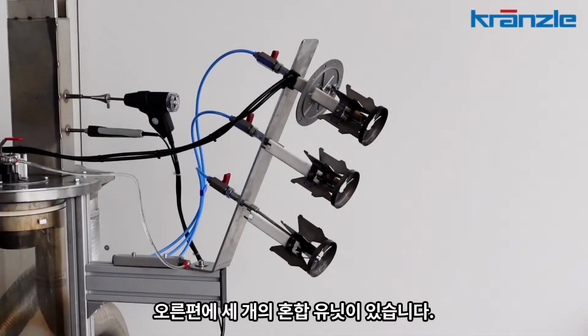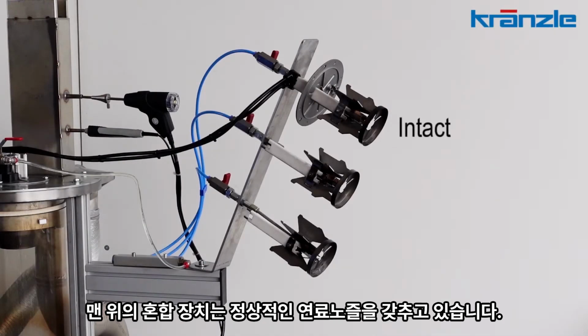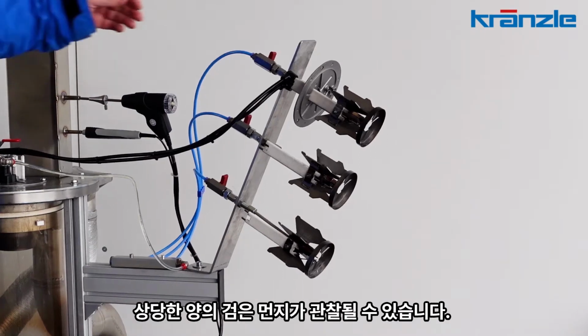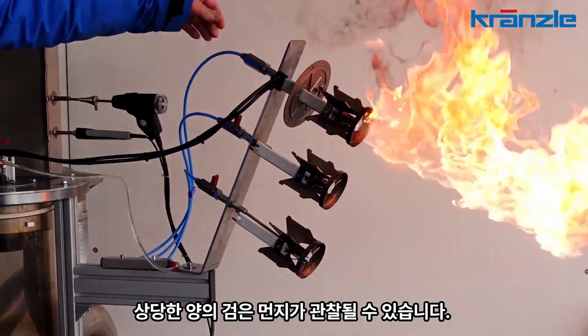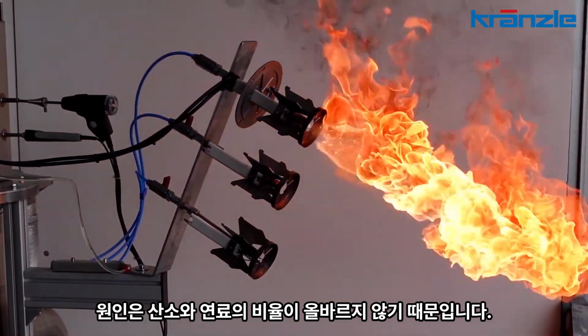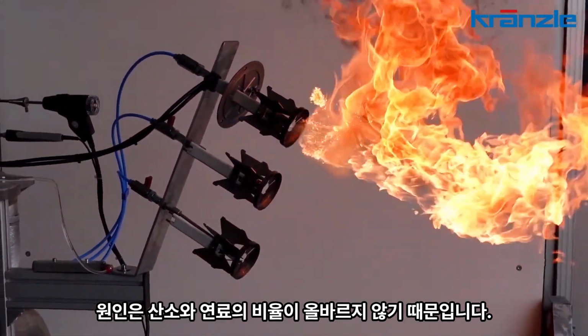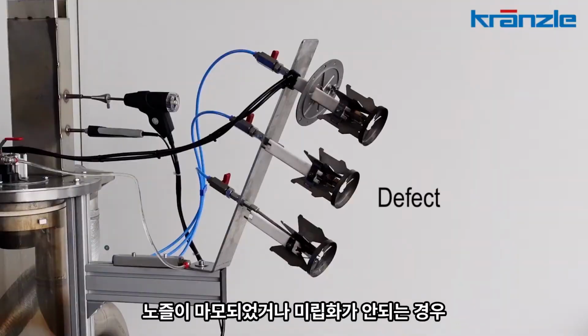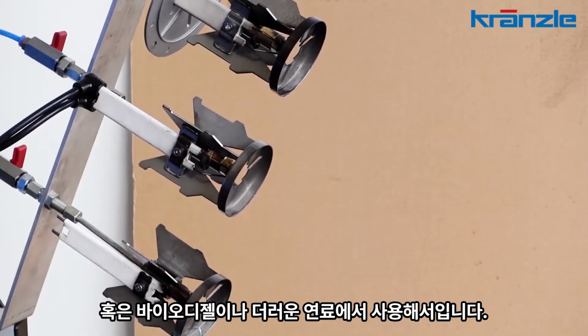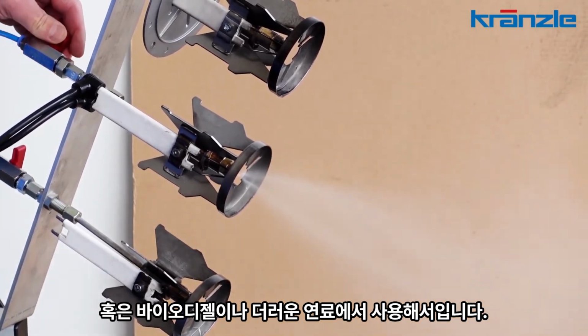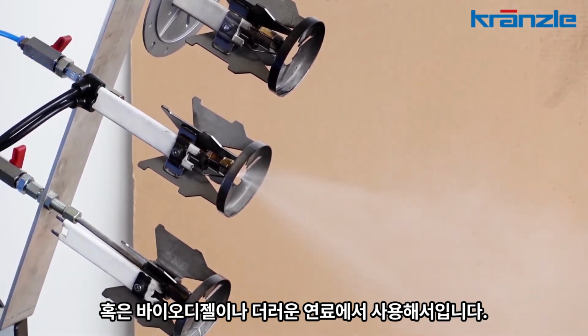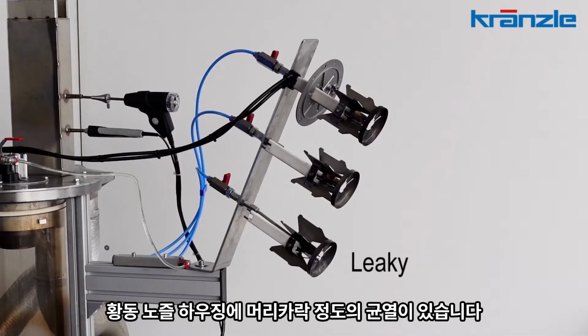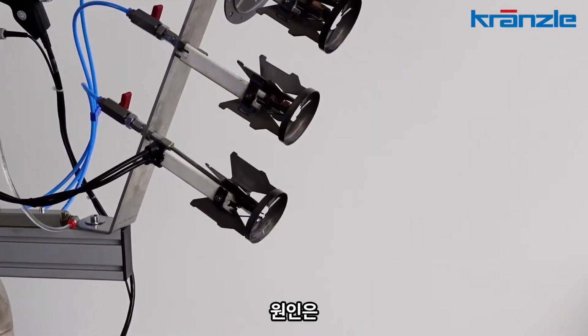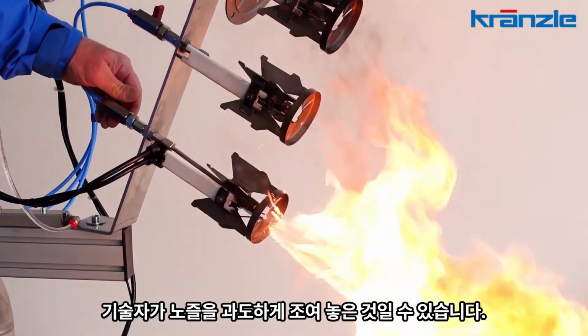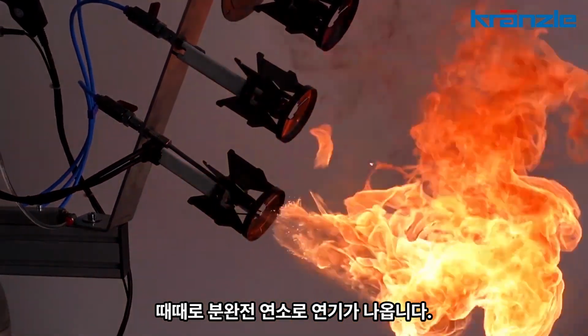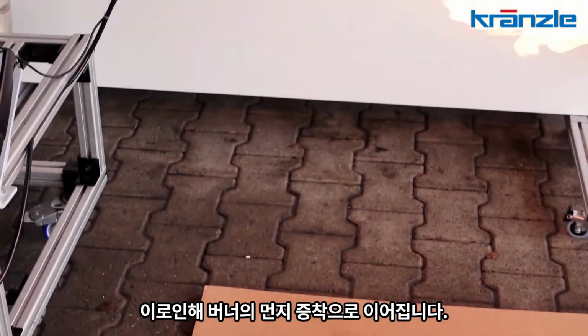On the far right are 3 mixing units. The top mixing device is equipped with an intact fuel nozzle. In contrast to the flame simulator, a relatively large amount of black soot can be observed despite a correctly atomized nozzle. The reason for this is that the ratio of oxygen and fuel is not correct. With the middle mixing device, the fuel does not ignite because the nozzle is worn or does not allow fine atomization from biodiesel or dirty fuel. The lowest mixing device has a hairline crack in the brass nozzle housing. The reason for this may be that a technician over-tightened the nozzle. Thus, the heat exchanger works fine, but from time to time there is a smoke trail coming out. This leads to sooting of the burner.